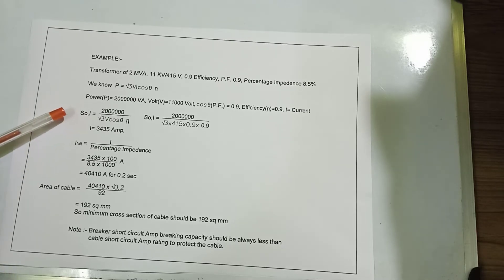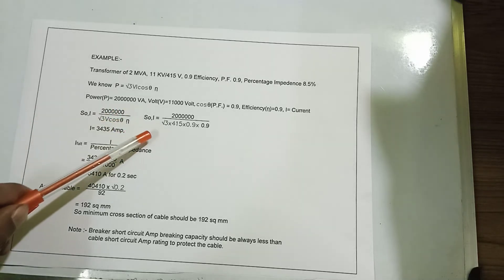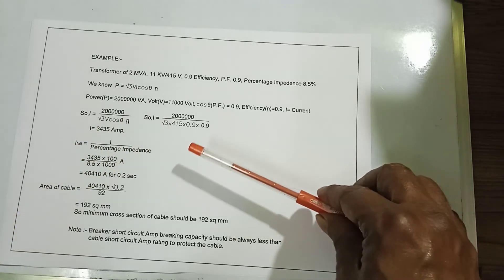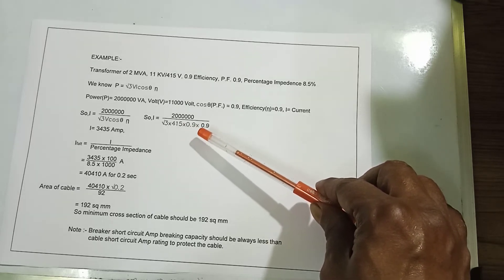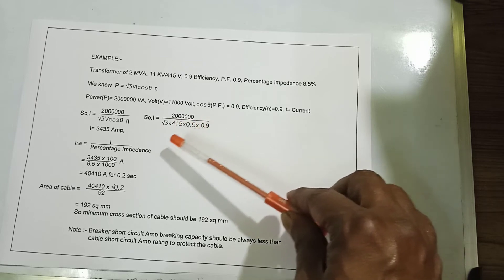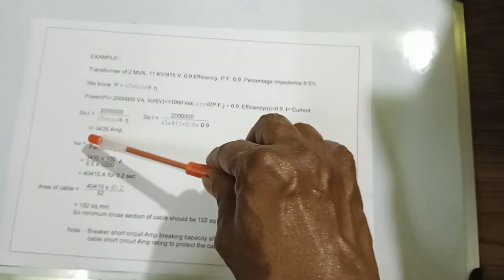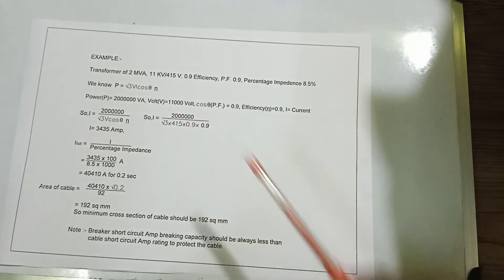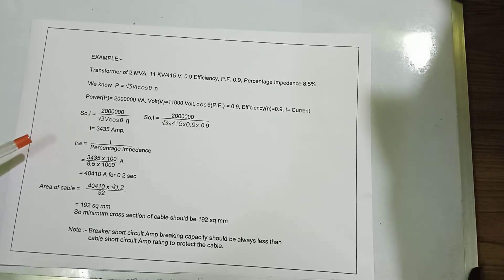Current I = 2 MVA divided by (√3 × 415 × 0.9 × 0.9), giving I = 3435 amperes.